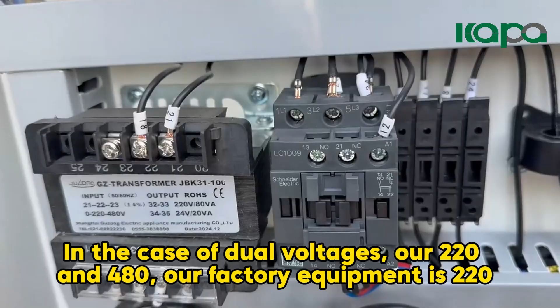In the case of dual voltages, our 220 and 480, our factory equipment is 220. So how do you make 220 become 480? Wiring method: the first step is to confirm the transformer. It is a dual voltage case, 220 input and 480 input.